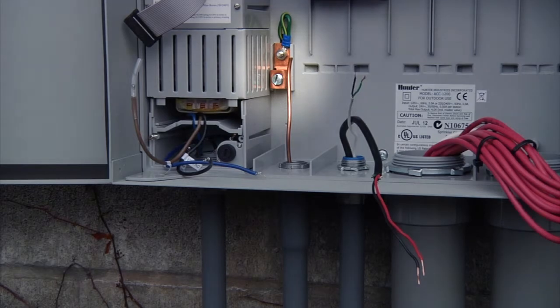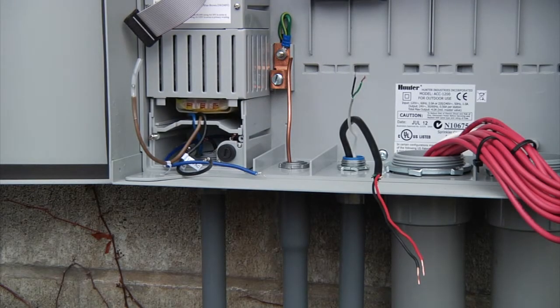This connection is designed for lightning protection of the controller. The grounding lug helps to protect the controller from harmful field surges, particularly during lightning strikes. Communication wires are especially susceptible to strikes, so grounding is particularly important in highly lightning-prone areas.